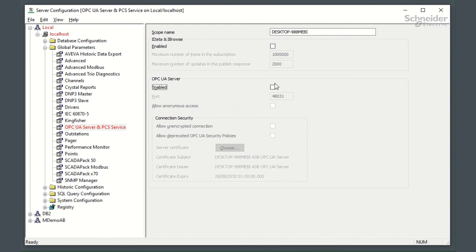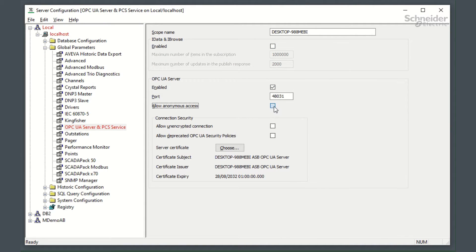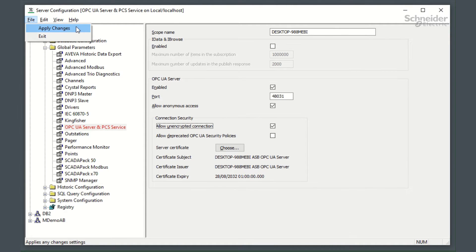You can configure the UA server through the server configuration tool, setting up security parameters. To do this, go to the global parameters page and select the OPC UA and PCS service node. Here are the settings for the OPC UA name and port. Enable the server, and if you want to use Geo SCADA usernames and passwords as credentials, then deselect anonymous access.